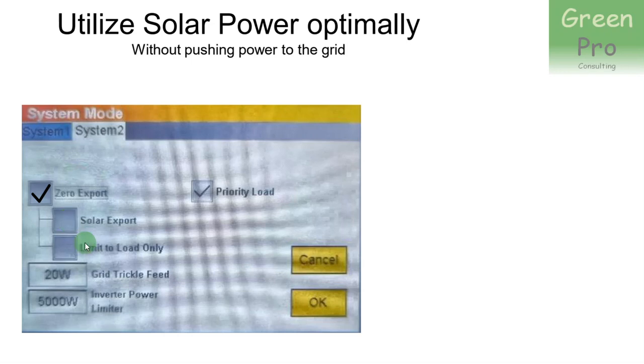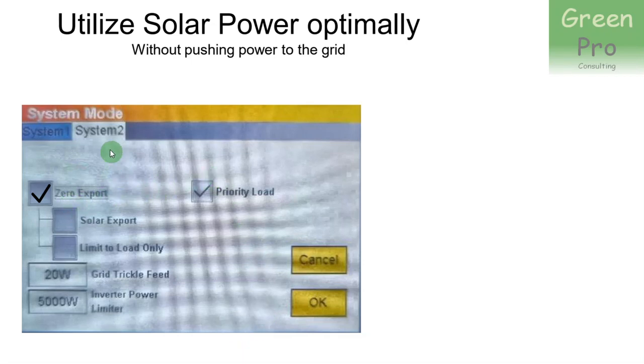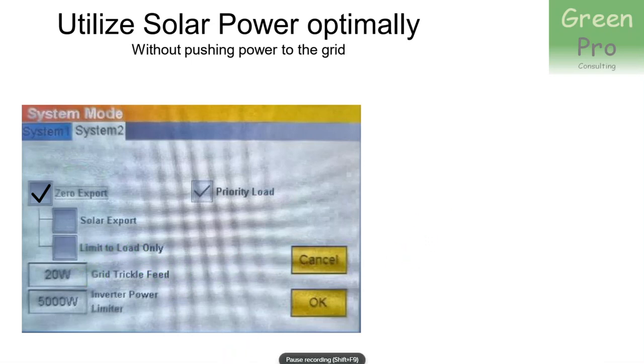If you don't tick solar export but you tick limit to load only, then effectively you're switching off the mechanism of pushing back power. This is the configuration you should set up in system mode 2 to optimally use your solar power.